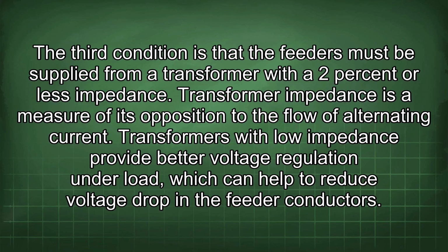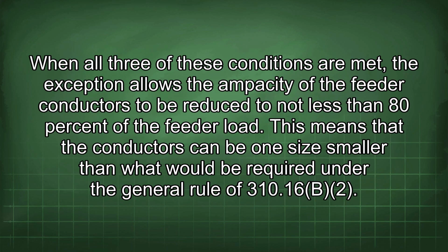or less impedance. Transformer impedance is a measure of its opposition to the flow of alternating current. Transformers with low impedance provide better voltage regulation under load, which can help to reduce voltage drop in the feeder conductors. When all three of these conditions are met, the exception allows the ampacity of the feeder conductors to be reduced to not less than 80% of the feeder load.